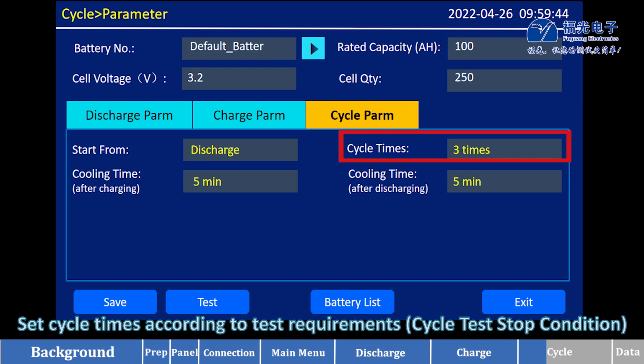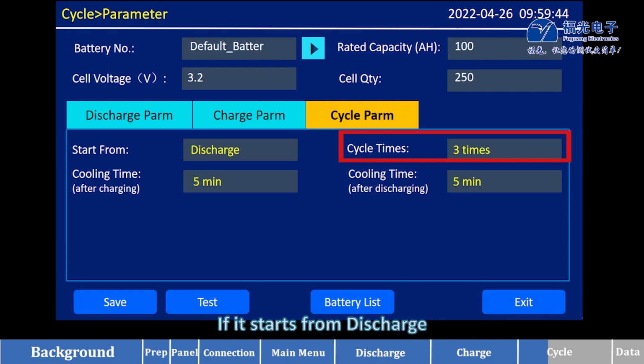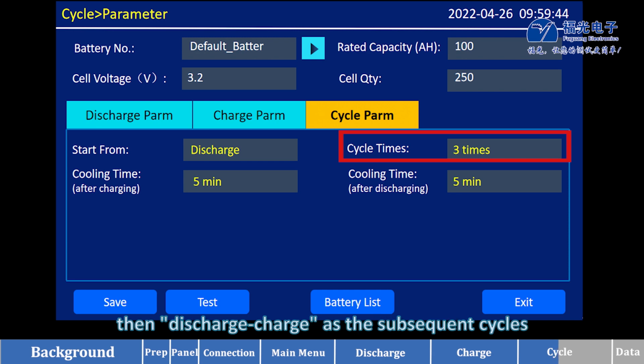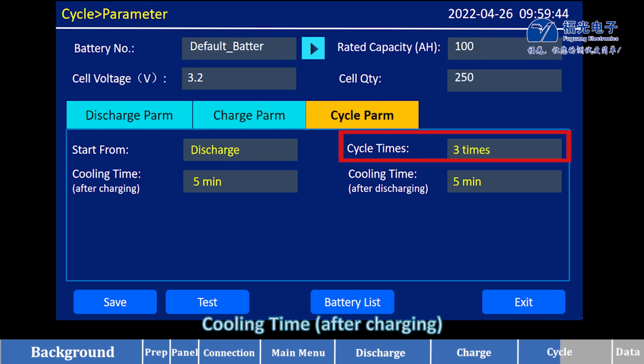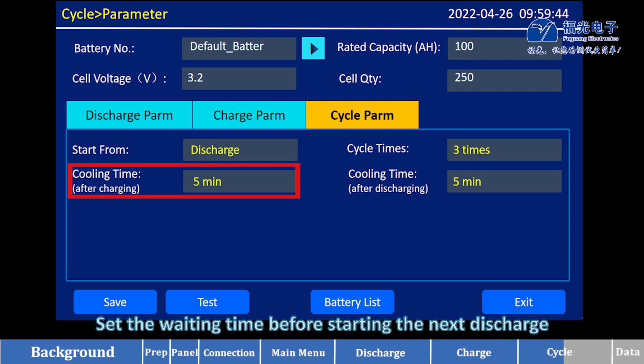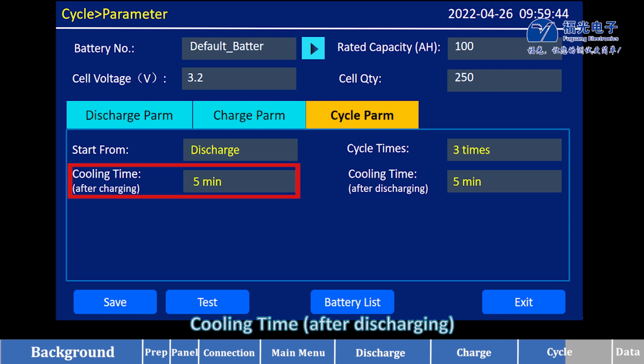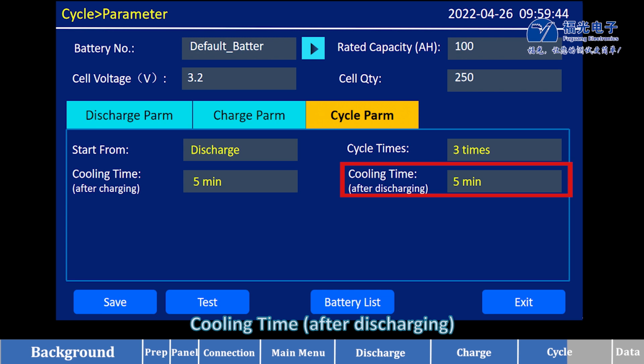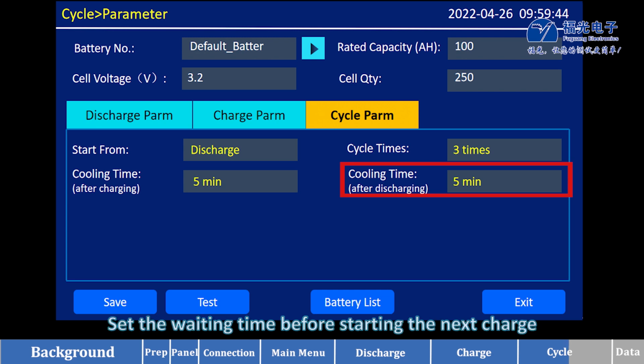Set cycle times according to test requirements. If it starts from discharge, the discharge-charge is one cycle. If it starts from charge, the charge-discharge-charge is the first cycle. Then discharge-charge as the subsequent cycles. Cooling time after charging. Set the waiting time before starting the next discharge. Cooling time after discharging. Set the waiting time before starting the next charge.